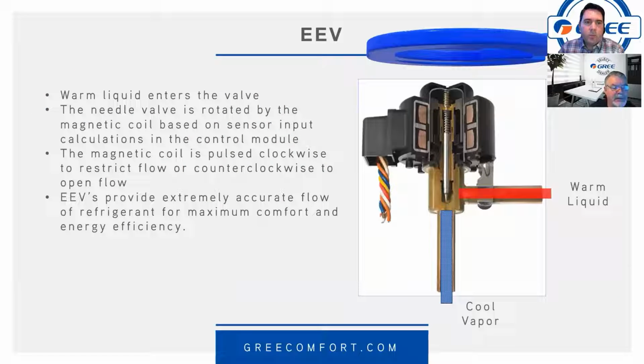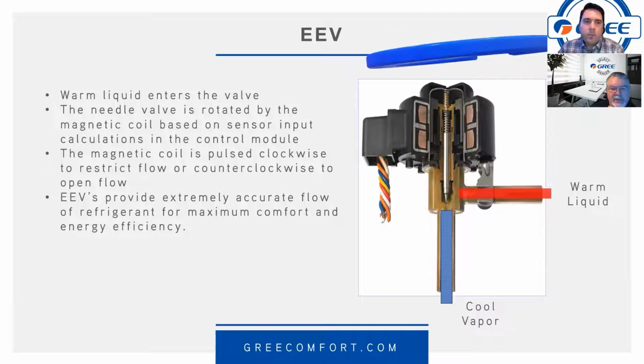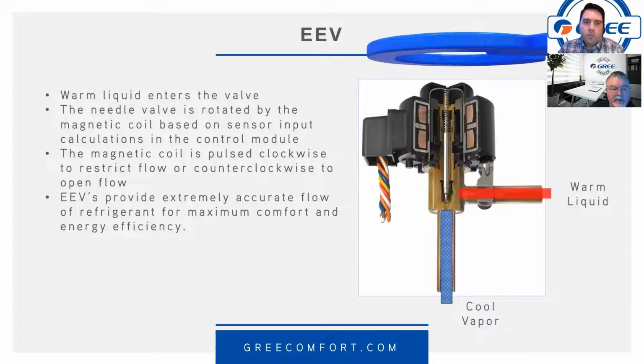So the way this thing works is warm liquid is entering in, and the needle valve rotates by the directional pulsations given to the magnetic coil. It spins clockwise to close the needle down, spins counterclockwise to open the valve up, and they provide extremely accurate refrigerant flow, with 480 steps to be fully open. 0 to 50, they call that fully closed, but then there's 480 steps for this thing to open and close within this range. You can see it's a real tiny little needle valve, and these things close off completely. At system startup, you'll hear that little ticking sometimes if you're outside, tick, tick, tick, tick. That's that valve driving all the way closed before it receives information from the controller and decides how much it needs to open or close.